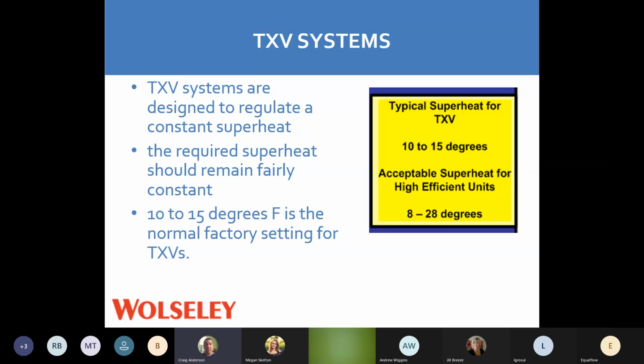TX systems are designed to regulate a constant superheat like we talked about. It's going to move up and down. It's going to try to keep the required superheat constant. So typical superheat is between 10 to 12 degrees. Check out your unit. Some of the higher-end units are a little bit different, but this is a typical reading that you're going to get for a TX system.